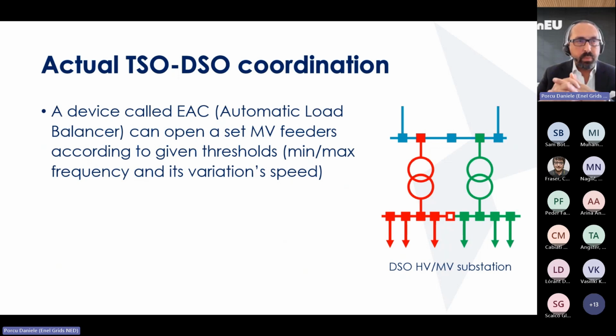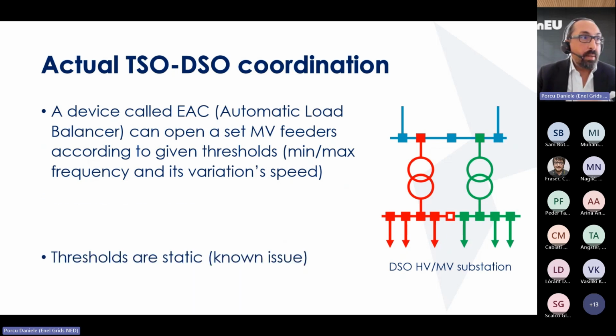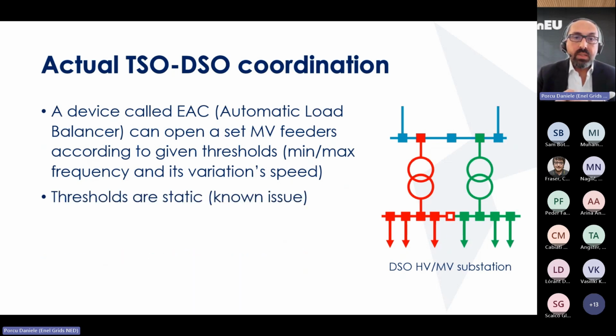What happened is that with the pressure of distributed generation, this kind of relay, this kind of tool, started to show its limitations. One of the limitations is that the thresholds or set points are updated once or twice a year.